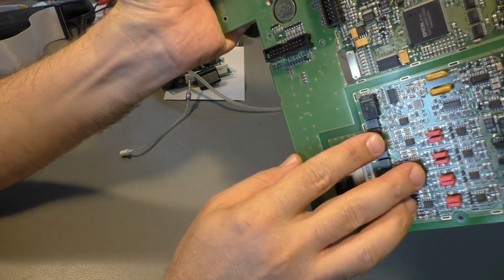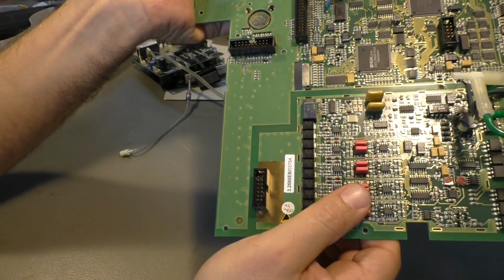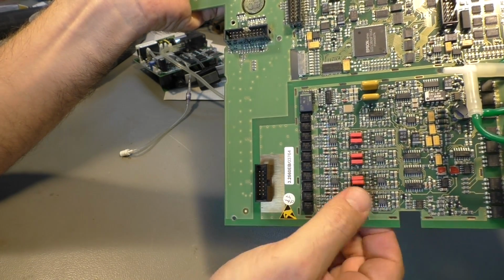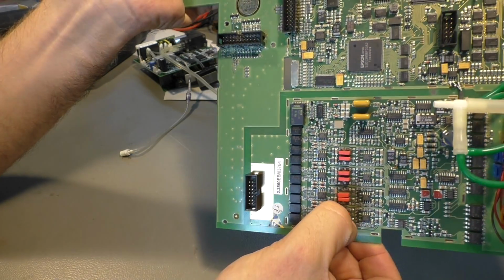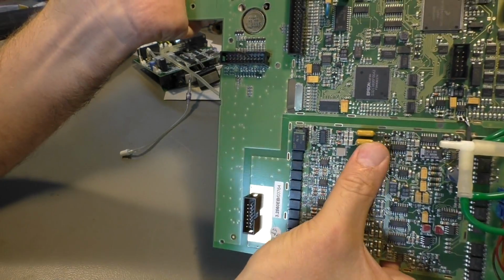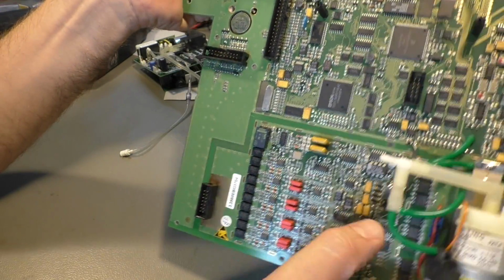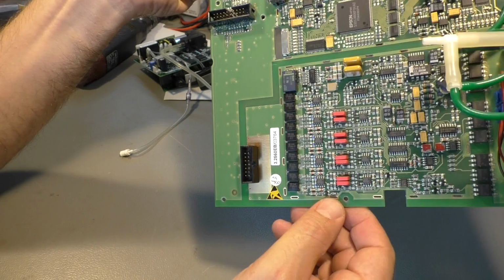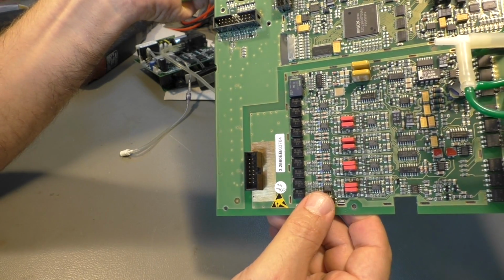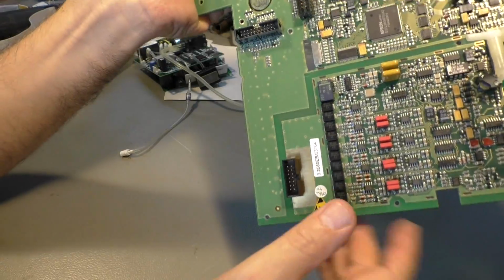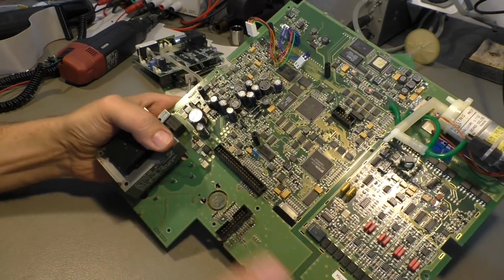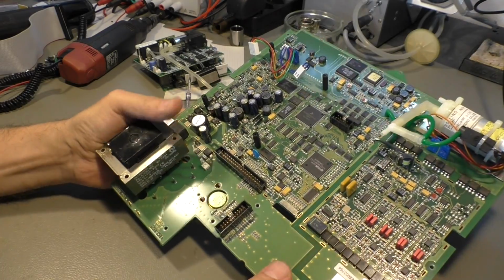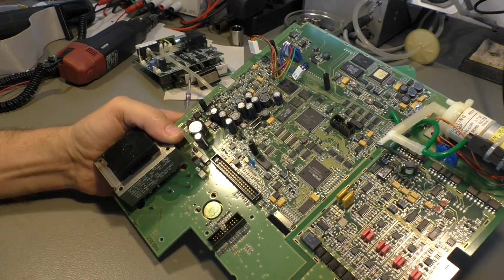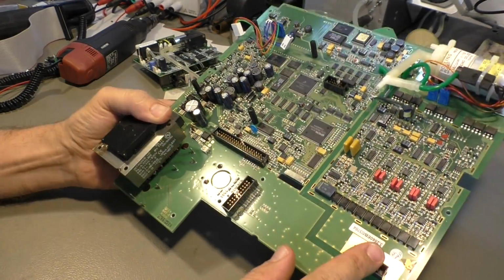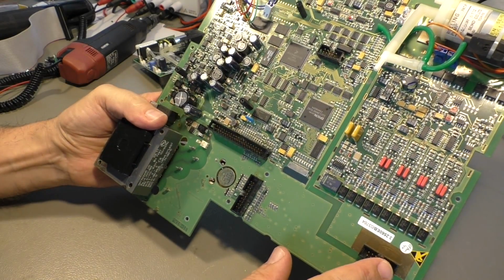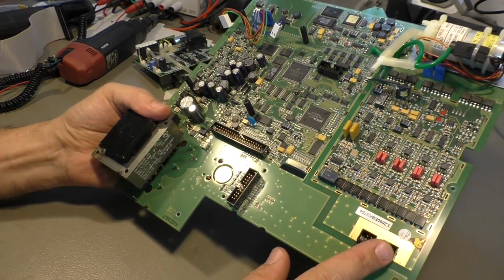because these medical monitors here are made to stay on the patient. For example, when they get a shock, an electric shock from the defibrillator. These defibrillators work with voltages up to 1000, maybe even more volts. And of course, in an emergency, you don't have the time to remove all the electrodes and everything before you can give the patient a shock. Everything has to go fast, so all these inputs are protected against that. Minimum protection is 5 kilovolts for all the inputs.